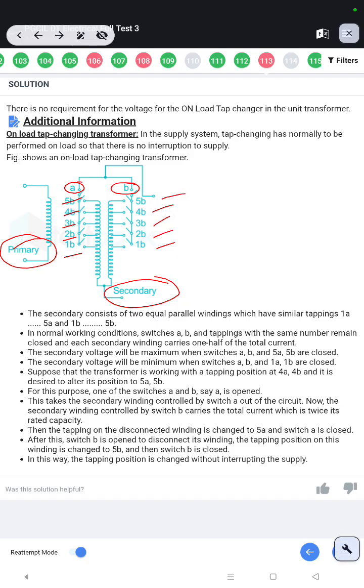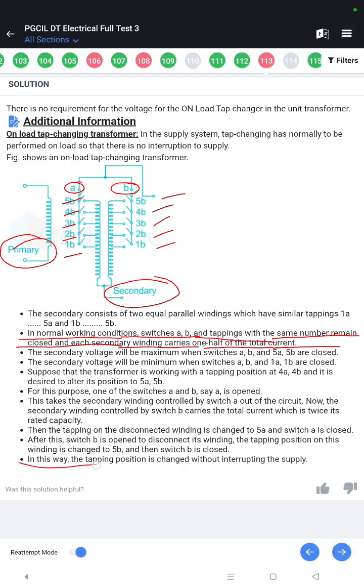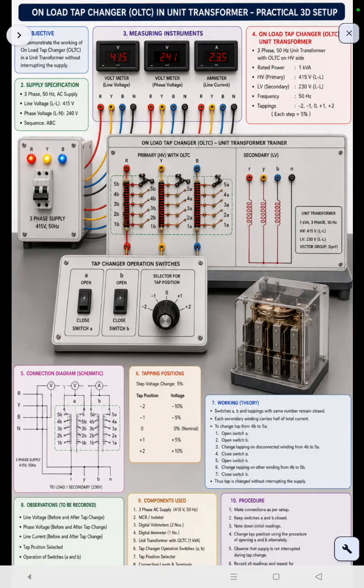In normal working conditions, switches A and B and tappings with the same number remain closed, and each secondary winding carries one half of the total current. In this way, the tapping position is changed without interrupting the supply. On-load tap changer in unit transformer, practical 3D setup. Objective: measuring instrument.